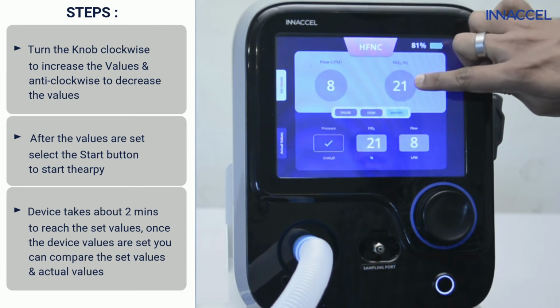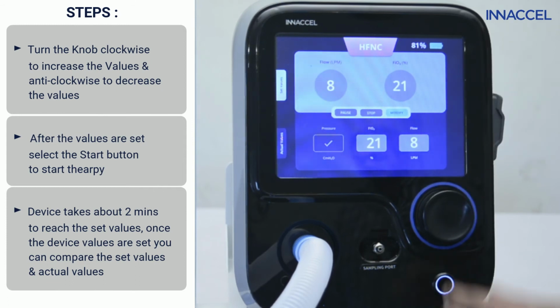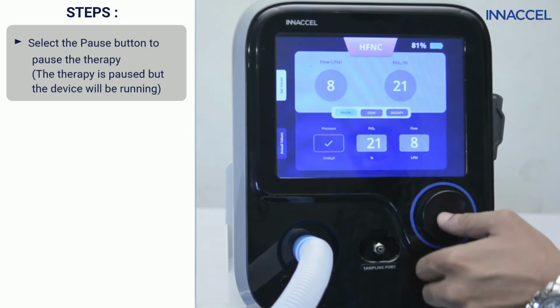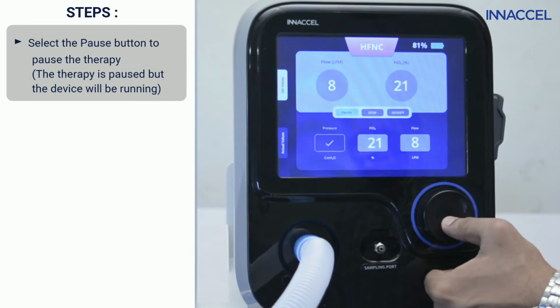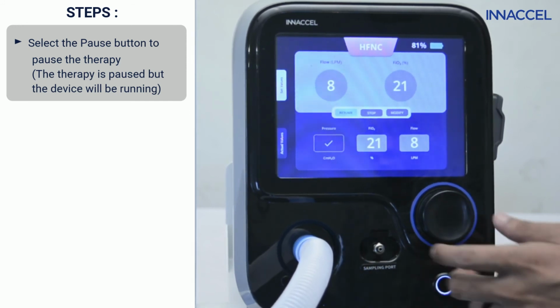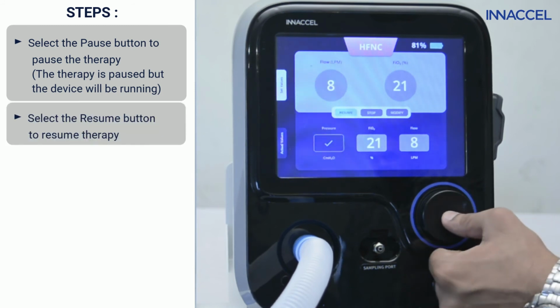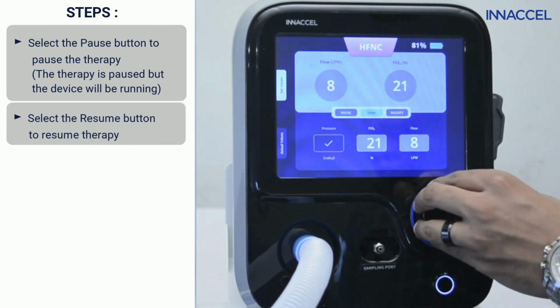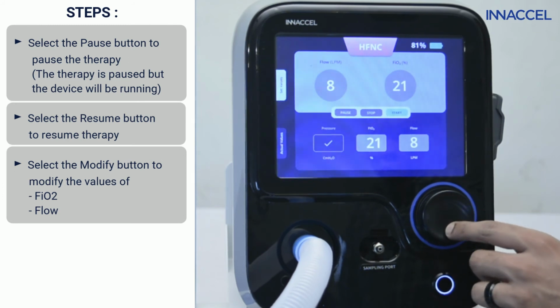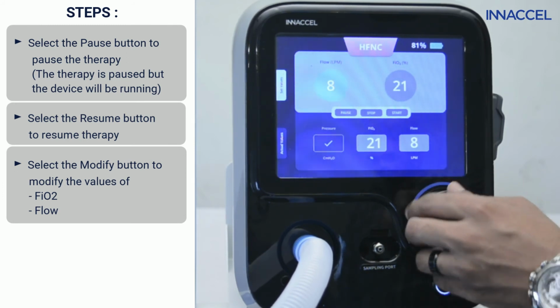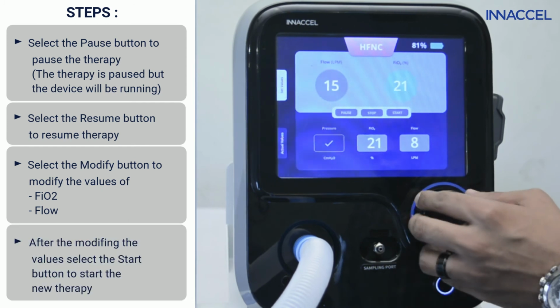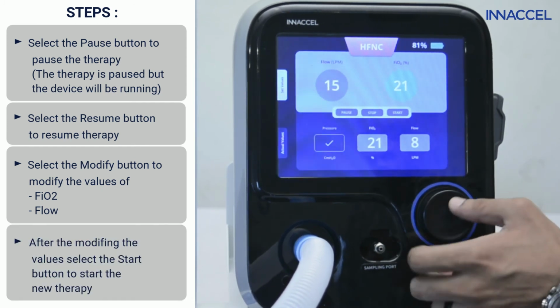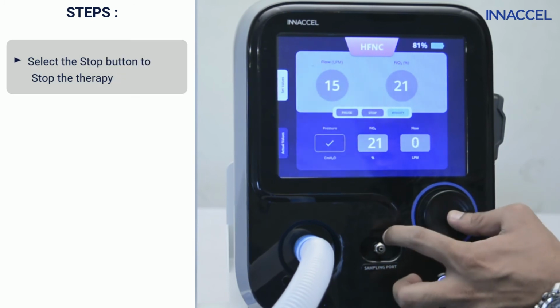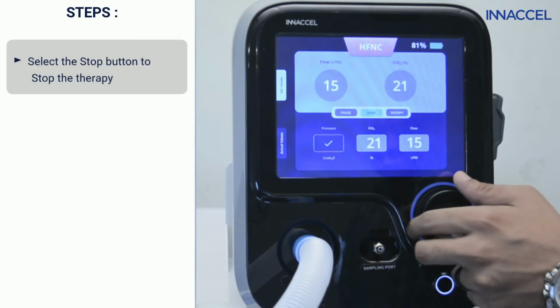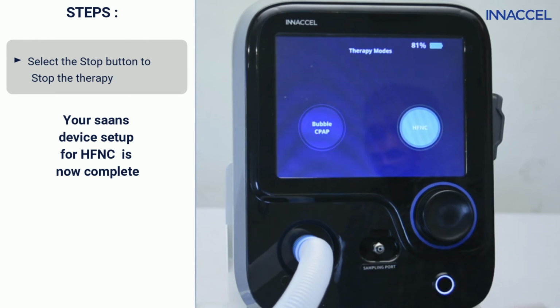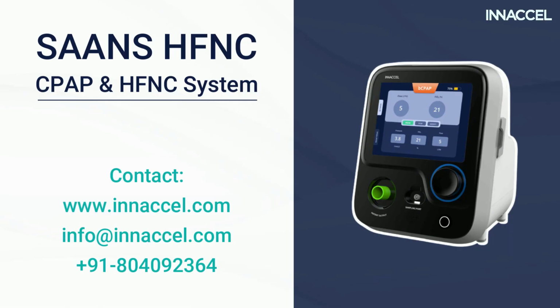The device also provides visual information to compare the set and actual values. You can pause the therapy by pressing the pause button, but that doesn't turn off the device. It simply pauses the therapy. You can resume the therapy by pressing the resume button. The airflow as well as FiO2 values can be edited using the modify button. To start a new therapy with the new values, press start again. To stop the therapy, press the stop button. Your SAANS device setup for HFNC is now complete.